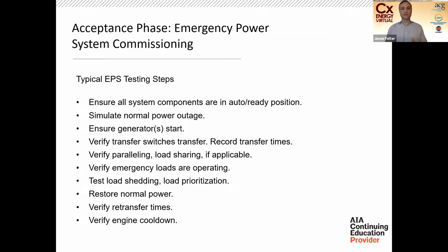So Mark took us through design. We've taken that design information and owner expectations and incorporated it into the commissioning plan. And then we have met with the installer and implemented an approach: we're going to commission this here, and this here. And at the end of it all, after we've vetted the components, we're going to test the emergency power system. And this is where the sequence comes into play.